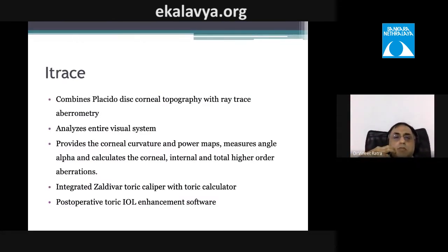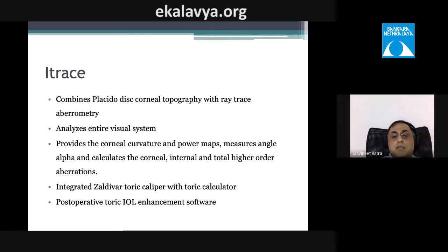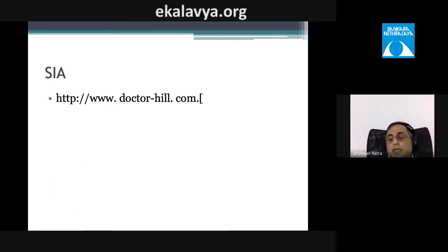The iTrace system combines Placido disc corneal topography with ray-traced aberrometry. It analyzes the entire visual system — corneal curvature, power maps, angle alpha, higher-order aberrations — and includes a built-in toric calculator. If you have iTrace, you can enter data directly and it will determine the correction needed, rather than using astigmatismfix.com.